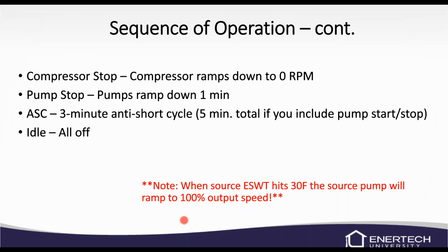When the call is done, the compressor will stop and ramp down to 0, and then your pumps will ramp down about a minute afterwards. Then on the screen, it will say ASC, and there will be a 3-minute short cycle. Once that goes away, if the call has not come, it'll just say idle, so everything will be off. There is a total of 5 minutes on the Enertech short cycle, but you've got a pump ramp up for 1 minute and a pump ramp down for 1 minute, which adds to the 3 minutes. So it's 5 minutes total.